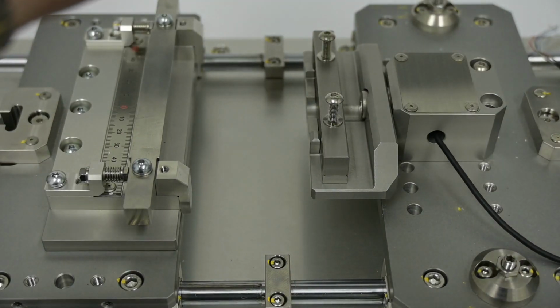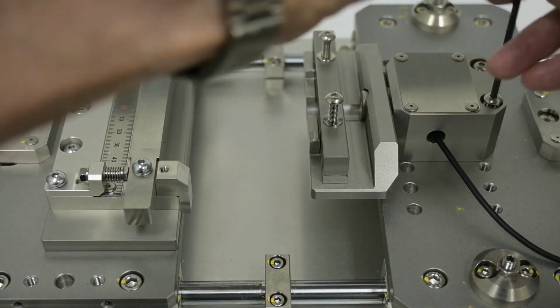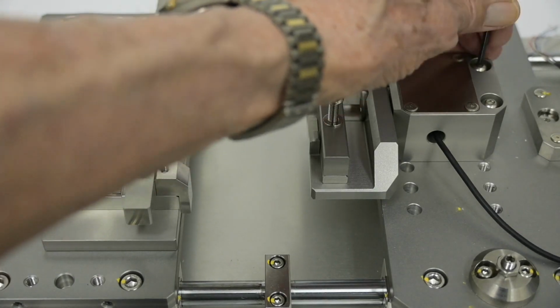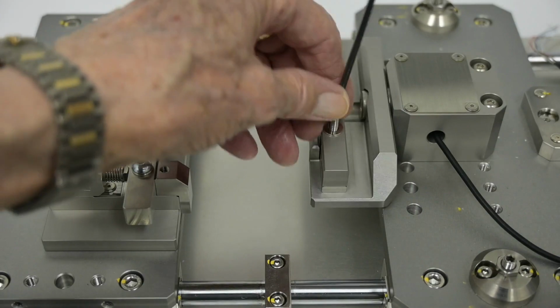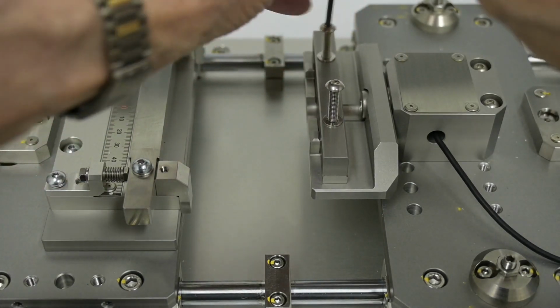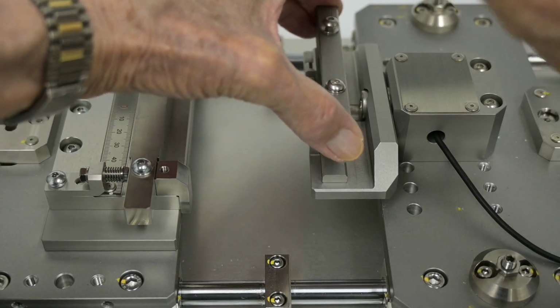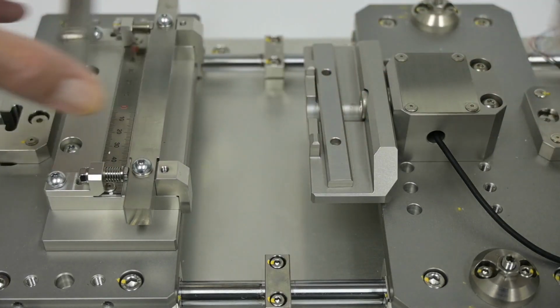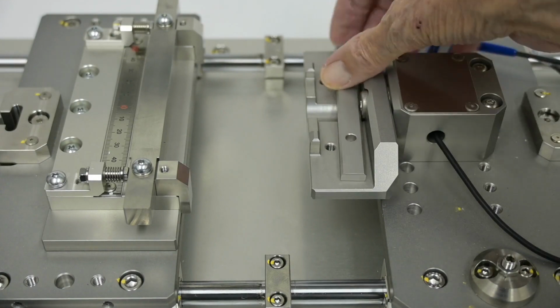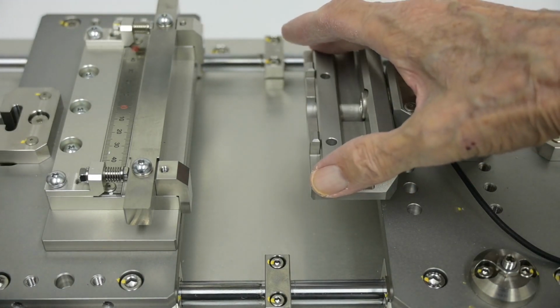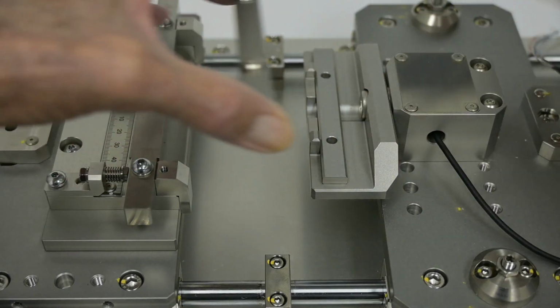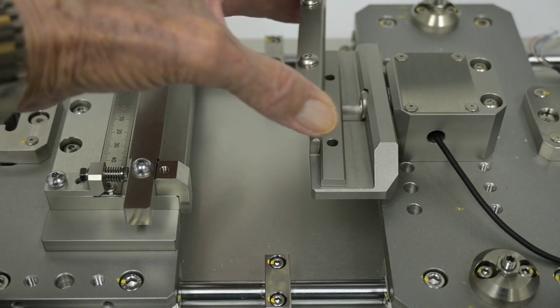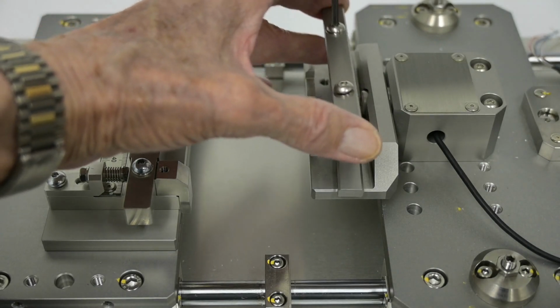Next, I will install the 2 long screws to secure the load cell clamp. Now we have completed the installation. These 2 screws are to clamp the sample. Removing the screws, the top bar lifts off. There's another thin bar at the bottom. The maximum width of the sample is about the distance between the holes. The beveled edges on the bars each face the sample, or each other. I will put the sample clamp back in place.